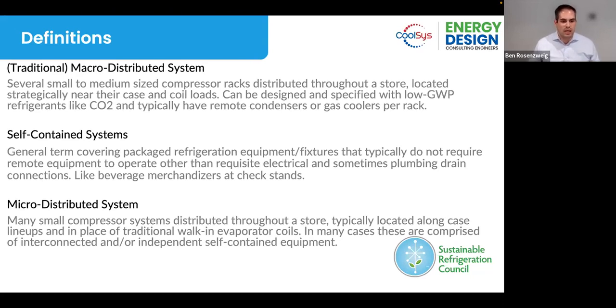Self-contained systems, to me, is a general term covering packaged refrigeration equipment and fixtures that typically don't require remote equipment to operate, other than for electrical connection and sometimes a plumbing drain. Even a product merchandising fridge at a check stand would qualify as a self-contained system, and frequently those only need to be plugged into an electrical receptacle.